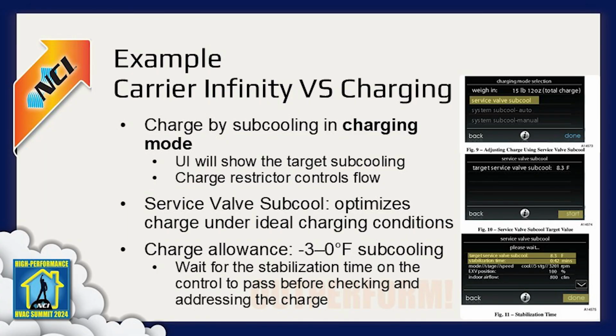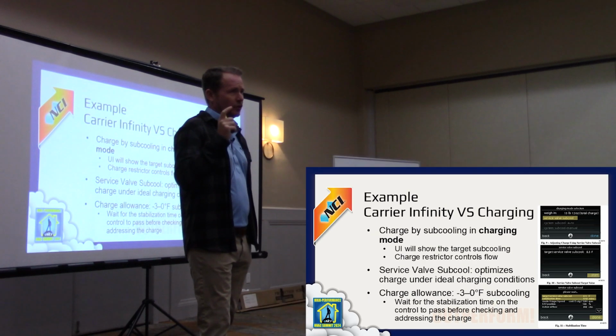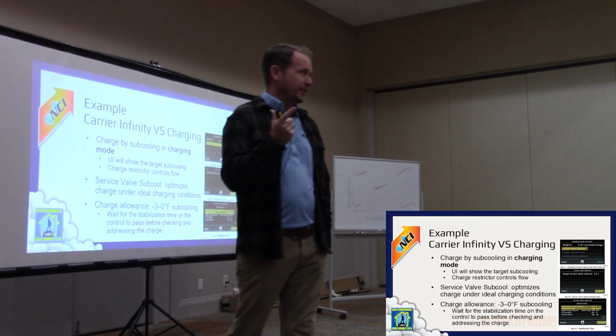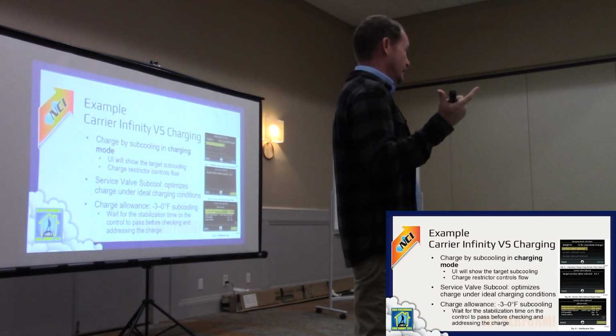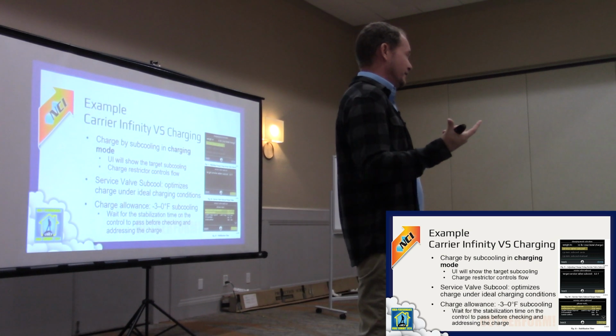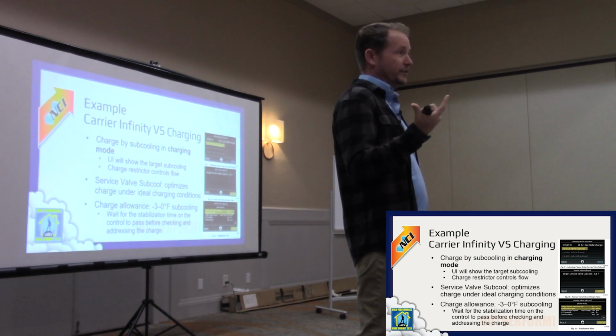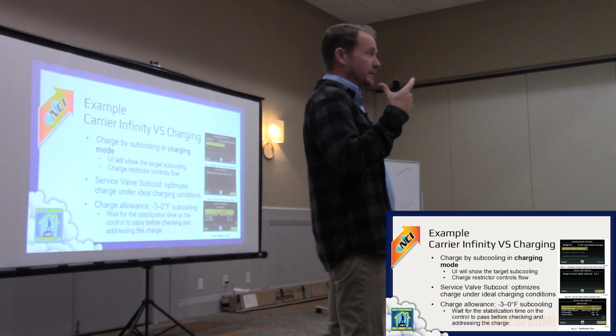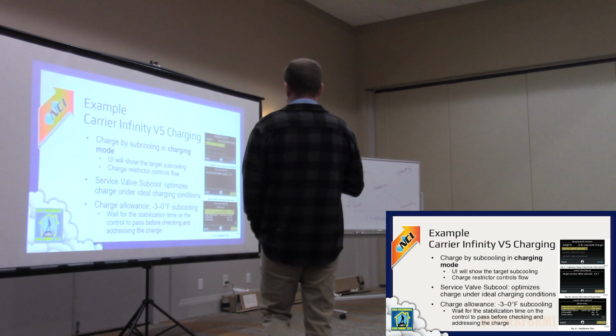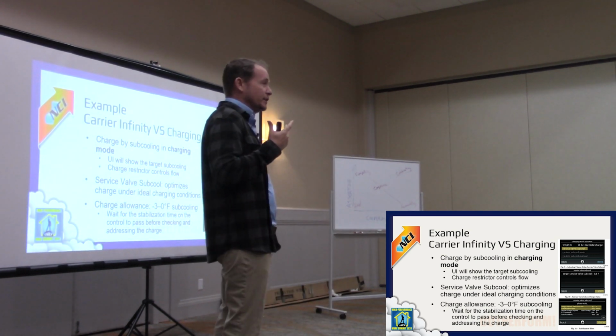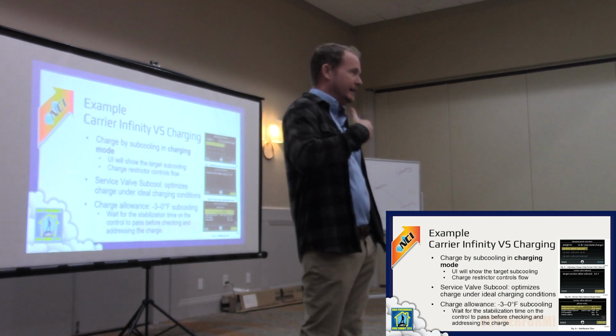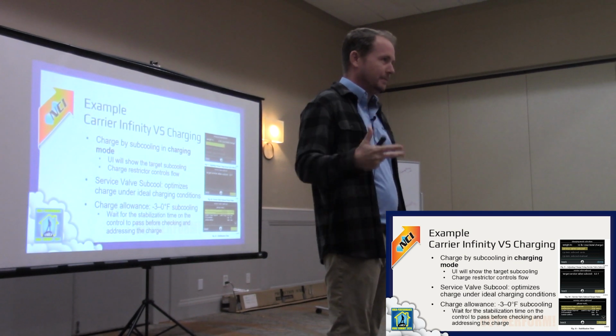This is just showing that specifically with this particular carrier unit - the type of system that's in my house - they have specific charging modes, and that's another RTFM thing. You need to know that, and if you don't know that the equipment you're putting in has a specific charging mode, there's a good chance your installers don't either. So you need to make sure they understand that. And that's not just true of charging it the first time - if there's a leak or you have to change something, you've got to do it every time.